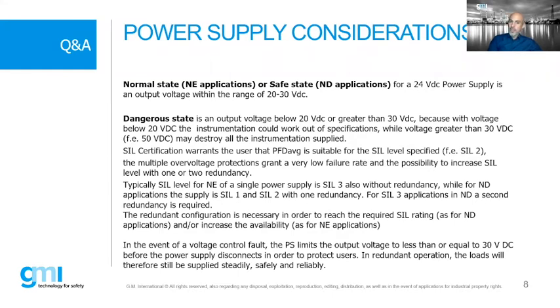The typical SIL level for normal energized, or single power, is SIL3, even without redundancy, as Massimo showed in the previous slides. But if you have a normal de-energized application, the standard is SIL1. If you want to reach SIL2, you need at least one redundant power supply. And for SIL3, you need a second redundant one, so 3 modules in order to reach SIL3. So we have seen that redundancy is important, also to increase the availability. Okay, we can go through that.